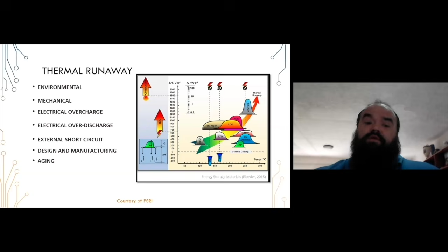When thermal runaway occurs in a lithium iron phosphate battery, the FSRI tested this, and they found that the percentage release of gases from this process is mainly composed of hydrogen at 49%, with hydrocarbons, carbon dioxide, and carbon monoxide making up the other 51%.